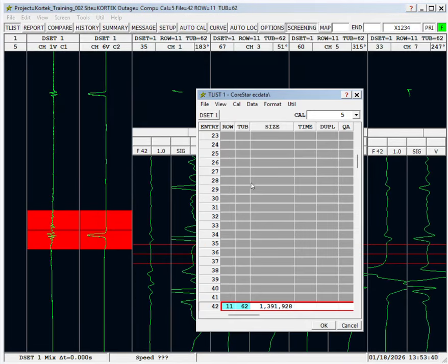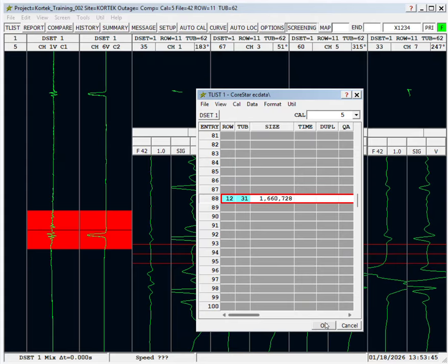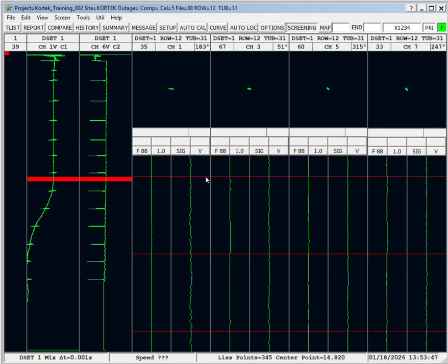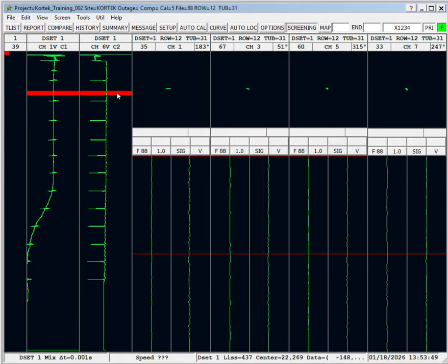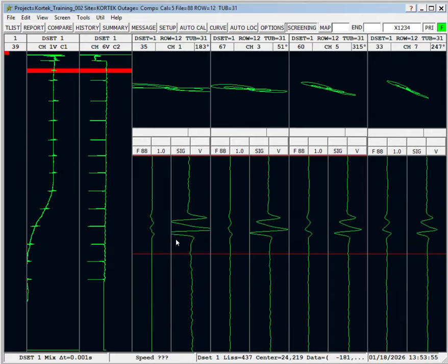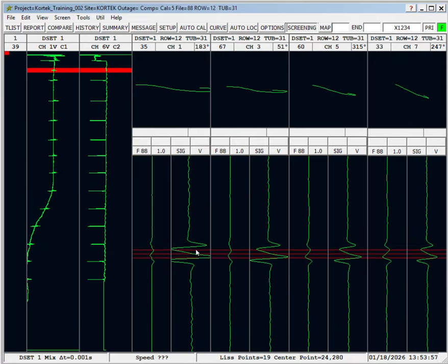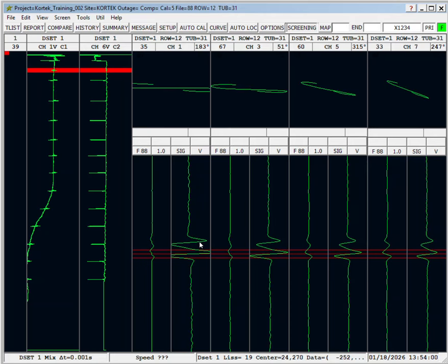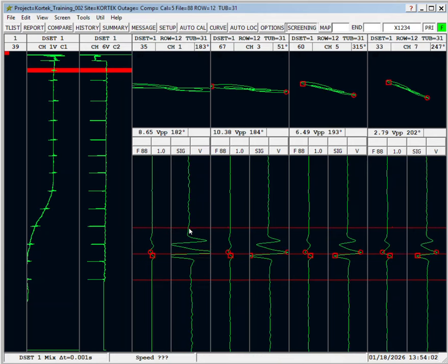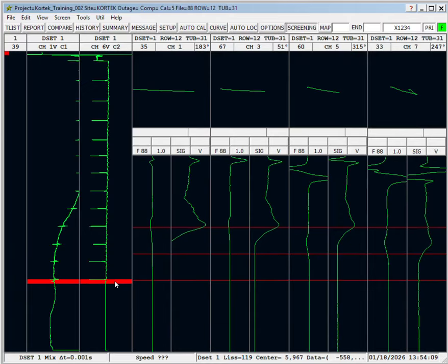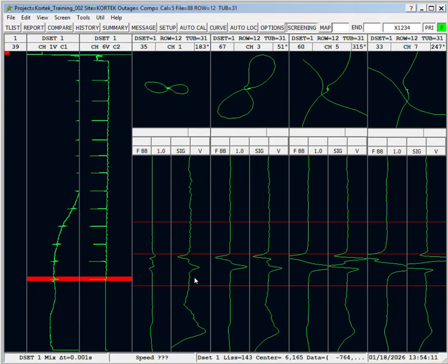All right. Next, we'll go to another tube. Balance on our strip charts. Again, lots of tube support plates. They all look the same. No problem with those supports. Oop, right there. We've got another set of paired dents in the free span. Notice how all these are looking pretty much the same. They're flat, more or less, on all of our differential channels. And then we've got a few more. We got one down there. Now see, that's just a normal looking tube support plate.